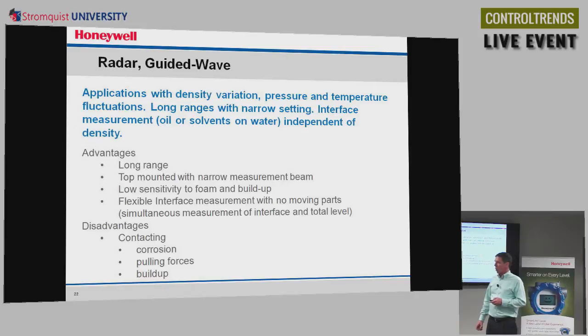Now, generally, you'd want to use guided wave radar in applications where you have a density variation, and fluctuations in pressure and temperature, even high pressures and temperatures, for long measurement ranges. We can go to 150 feet with a cable on guided wave, and maybe working through a narrow setting. So let's say there's a lot of stuff inside of a tank. The guided wave with a stilling well or with a coax can work over a narrow range. It's not going to be affected by obstacles that are in the tank.